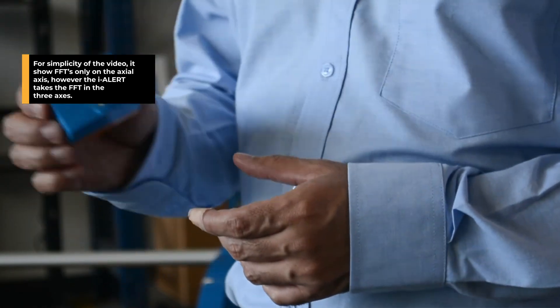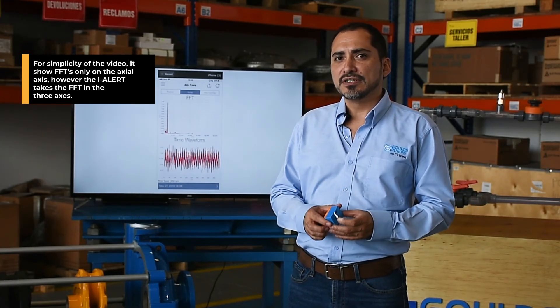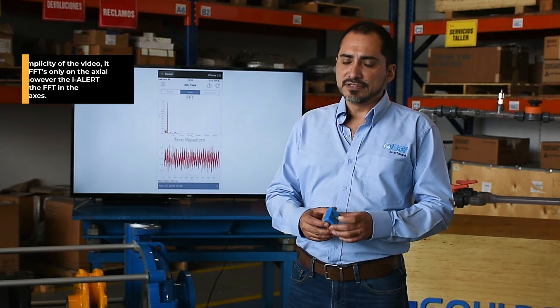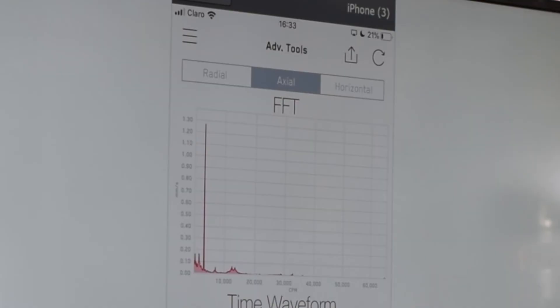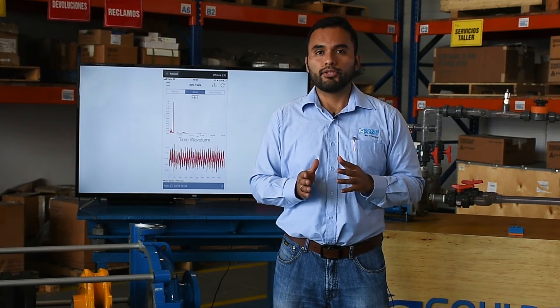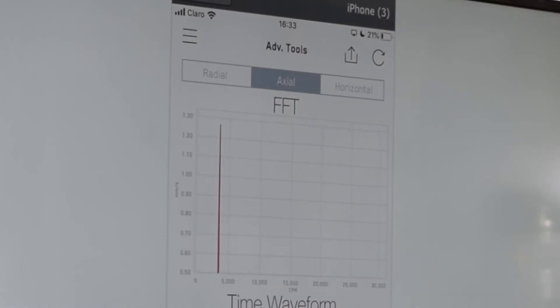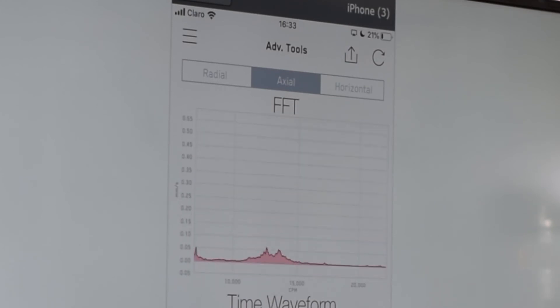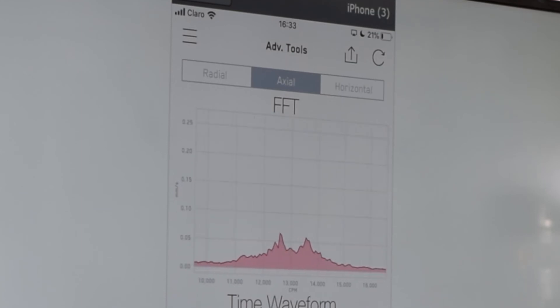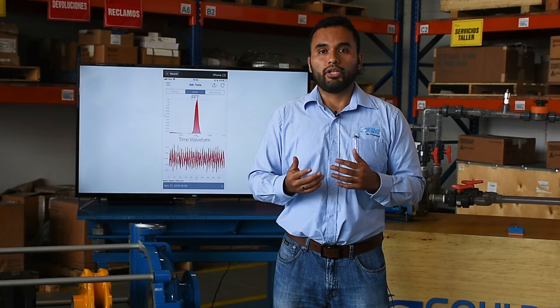That is to say, the moment we have an upset condition that warrants an alarm, the sensor takes a picture of the problem. The app gets the FFT which shows relatively low amplitudes, up to 1.3 mm per second. We know that at the vane pass frequency the amplitude is 0.5 mm per second. There is always some level of unbalance that can be seen at the speed of rotation, but in this video we want to focus on the hydraulic issues.